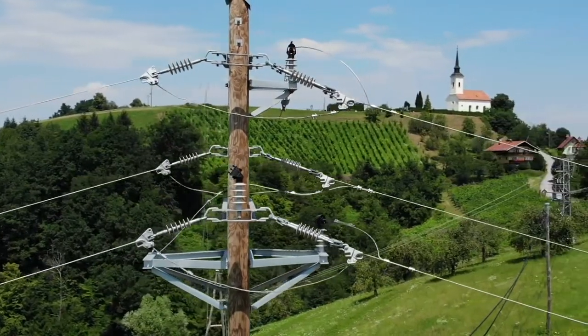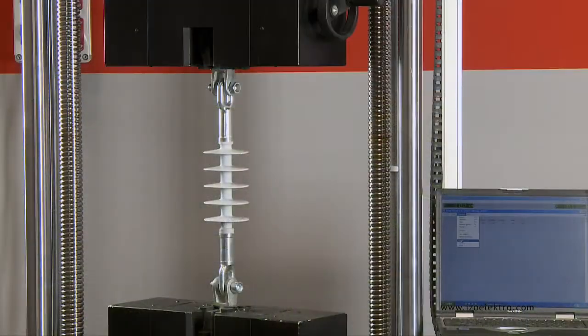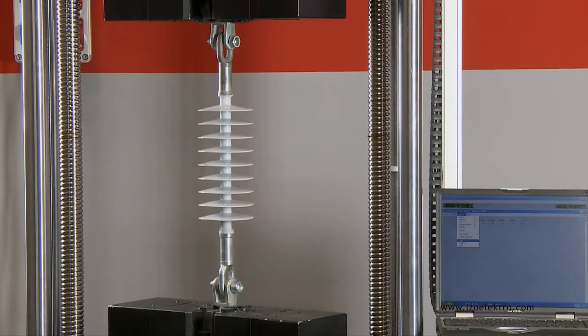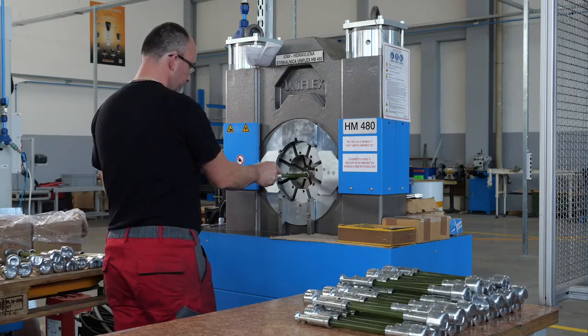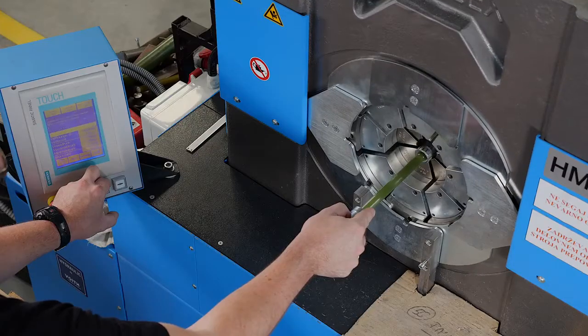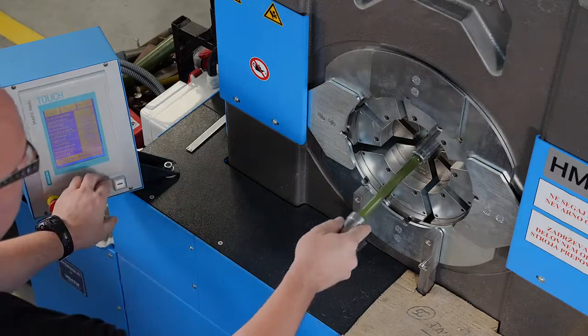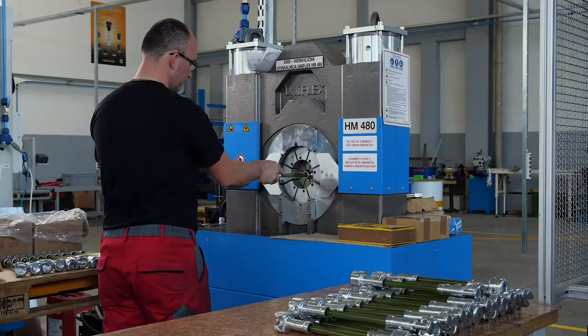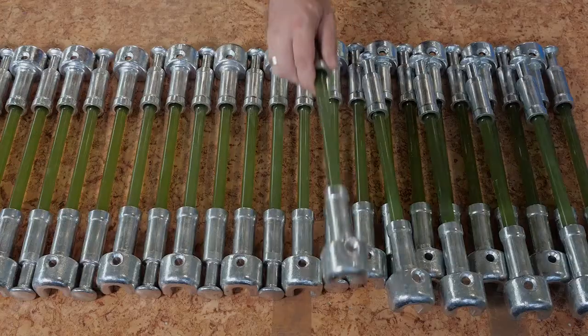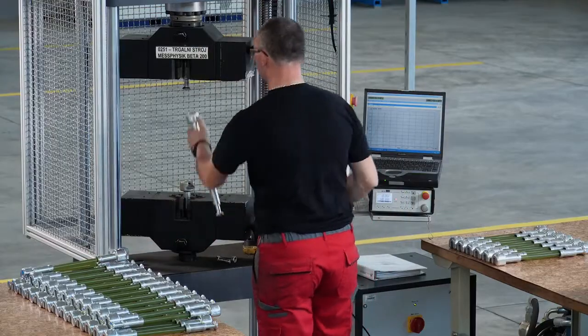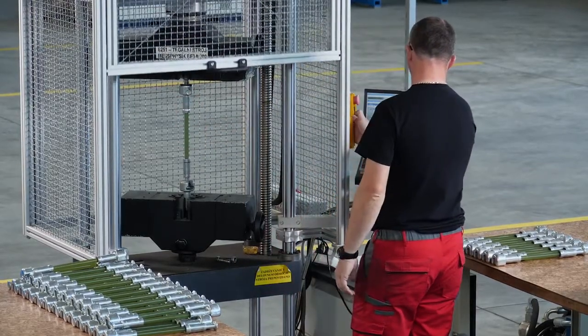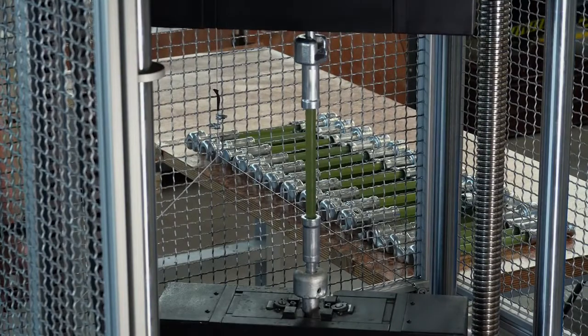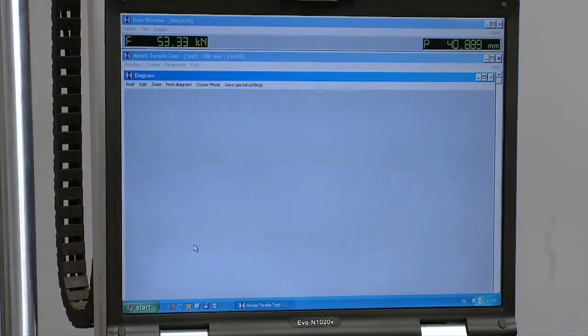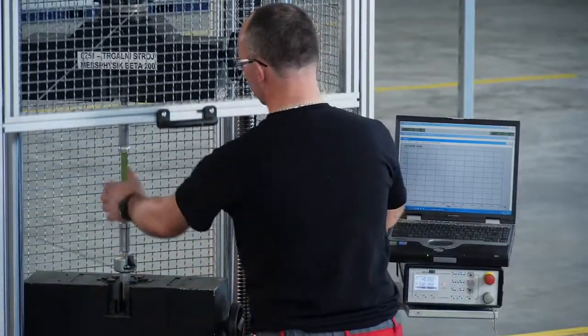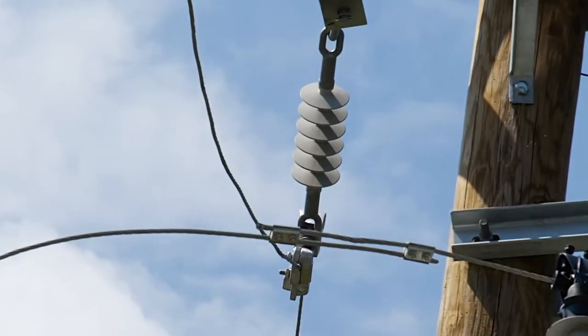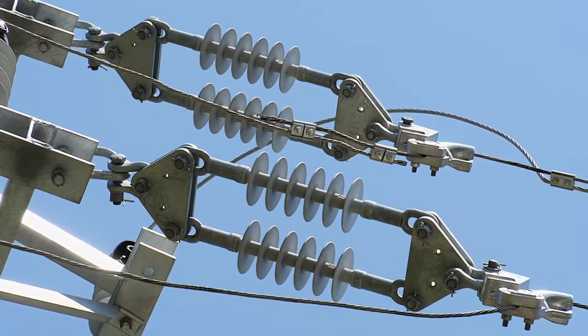Our array of products also encompasses tension composite insulators with a creepage distance of up to 1,200 millimeters. Particular attention in the manufacturing process is given to the pressing of metal fittings onto the epoxy rod of the insulator. A highly modern hydraulic machine with 8 pressing jaws and 3 different pressing modes is used for this purpose. In accordance with the standards, we also perform a tensile test on each insulator using a universal testing machine before siliconizing to ensure the fittings are adequately pressed onto the epoxy rod. Depending on the fitting type, the mechanical destructive force is 90 kilonewtons.